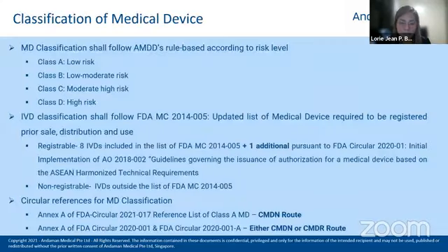Next slide, please. Now, how will you know the risk classification of your medical device? In the Philippines, the classification of medical device follows the AMDD ruling or the ASEAN Medical Device Directive according to risk level. So it's either Class A or low risk, Class B or low to moderate risk, Class C, moderate to high risk, and Class D or high risk.